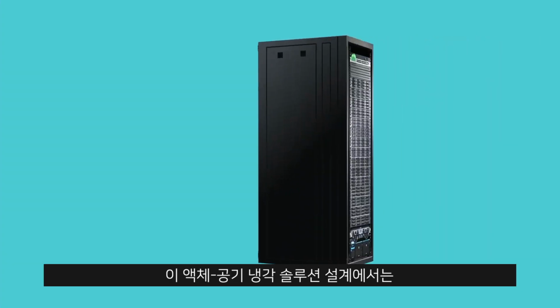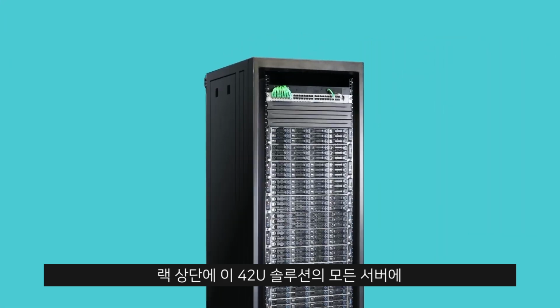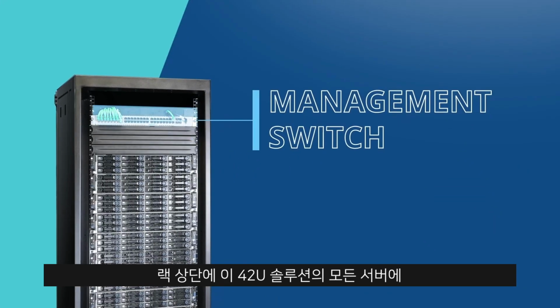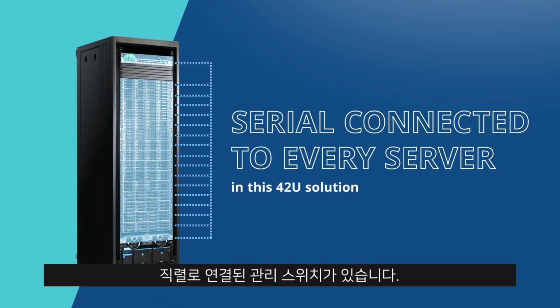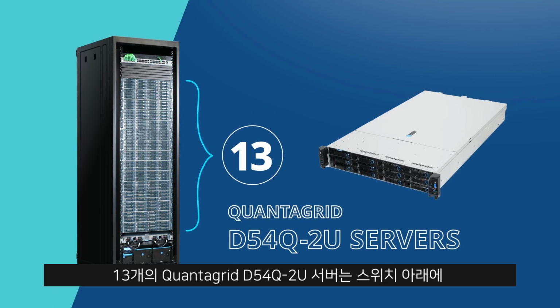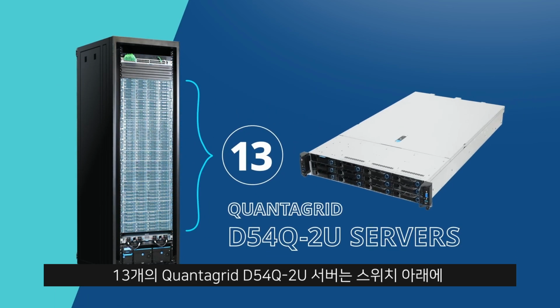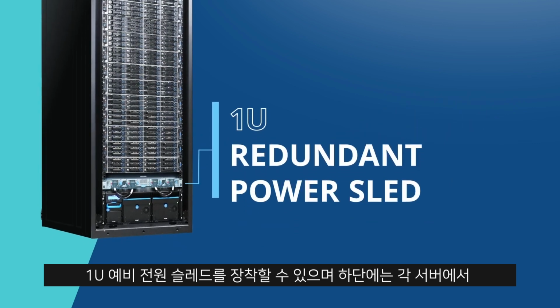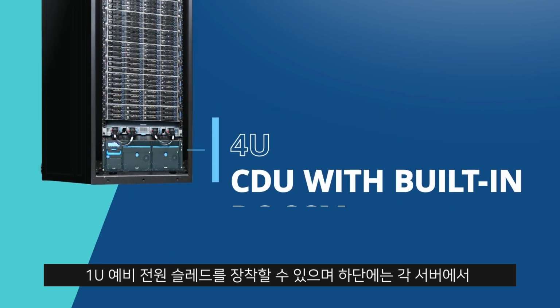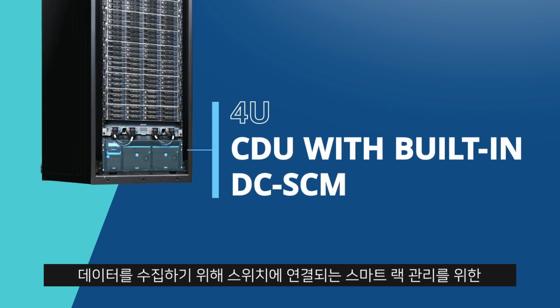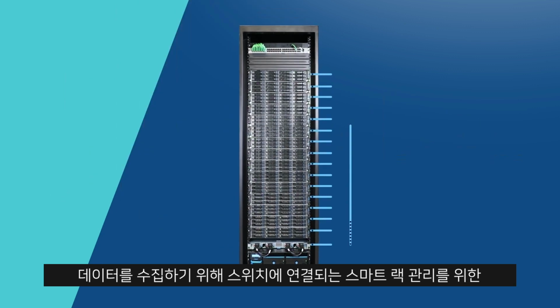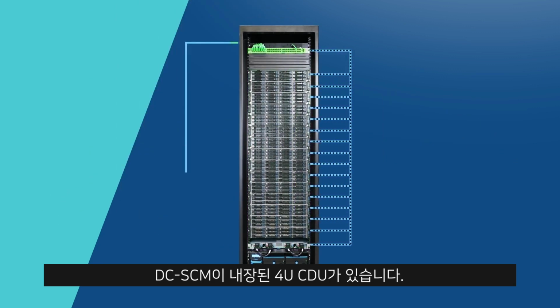In this liquid-to-air cooling solution design, at the top of the rack is the management switch, which is serial connected to every server in this 42U solution. 13 QuantaGrid D54Q-2U servers can fit beneath the switch, followed by a 1U redundant power sled, and at the bottom sits the 4U CDU with its built-in DC-SCM for smart rack management that connects to the switch to collect data from each server.